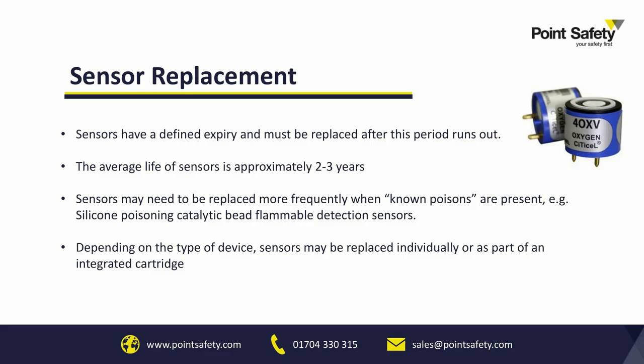The third main activity in servicing will be sensor replacements. Each sensor has a defined period and must be replaced after this period runs out. The average life of a typical sensor is approximately 2 to 3 years, although this does vary. Some of your most volatile gases will have a sensor life of a year. Typically, oxygen sensors will last up to 5, and flammable sensors can last longer if calibrated and serviced regularly.